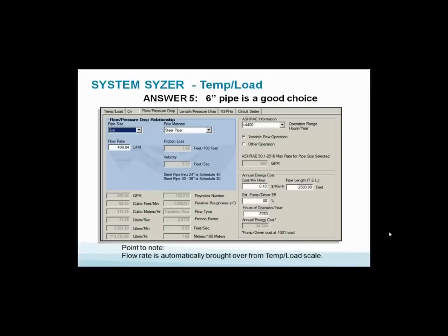In the right-hand column, you can plug in the hours of operation. In this case, we've got 10 cents a kilowatt hour. We plugged in 2,500 feet as the total equivalent length of pipe. If you're running year-round, you can change the hours of operation. You've got some way now to estimate the cost of running this system. I think you see a six-inch pipe is a good choice.